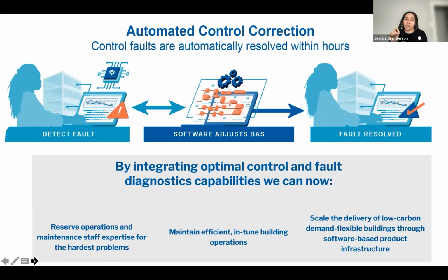Through this work, we're now able to short circuit that process of taking corrective action. So now through an operator approved automated response, we can find the problems, we can execute corrective action and confirm that the problem has been fixed, and do that in a matter of hours with minimal need for staff time. So this really brings together control and diagnostic capabilities, and that does a few things for us. We can free up staff time for the hardest and most interesting problems that merit their attention. We can keep those in-tune operations persistent over time.